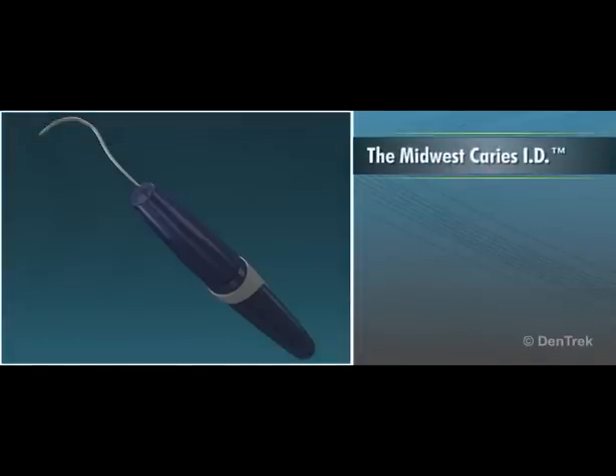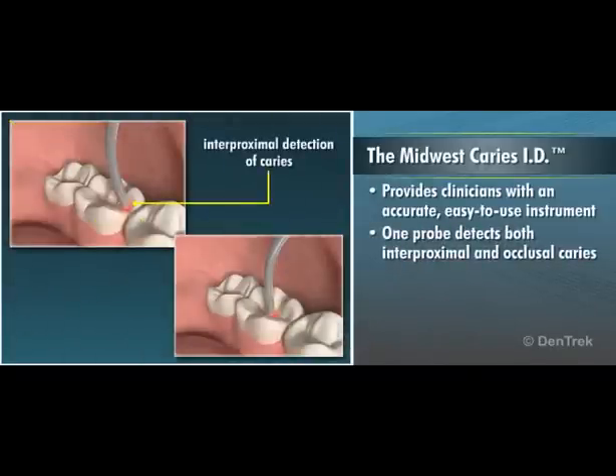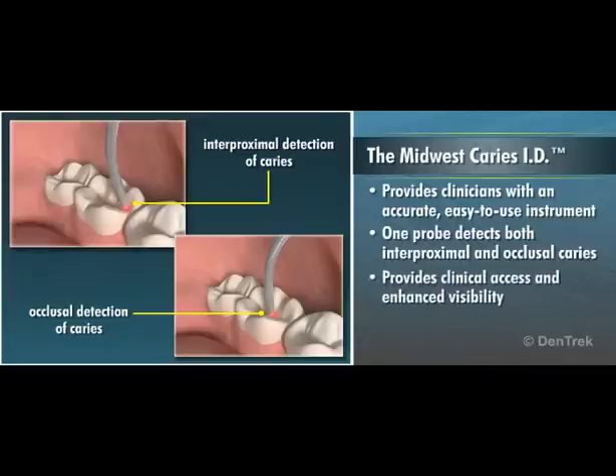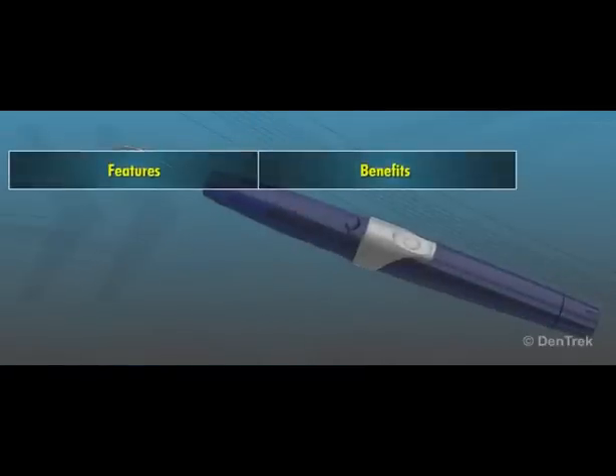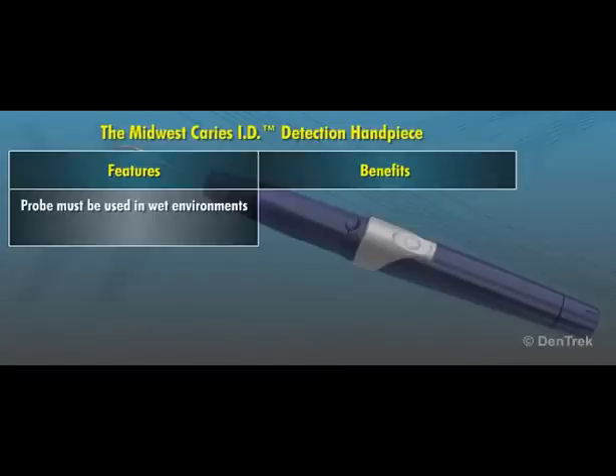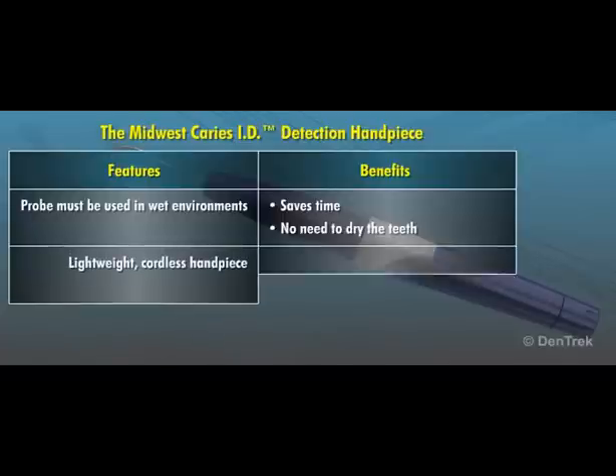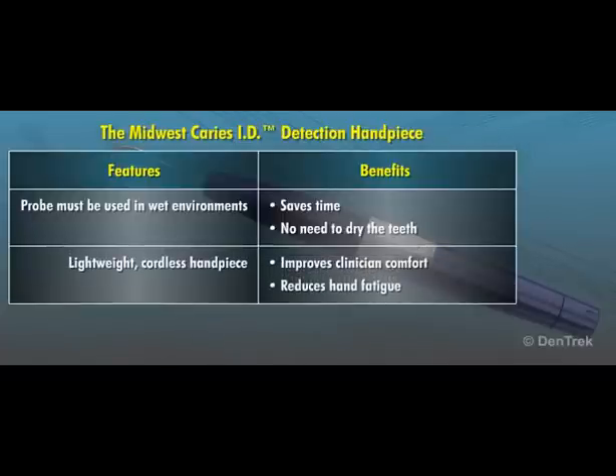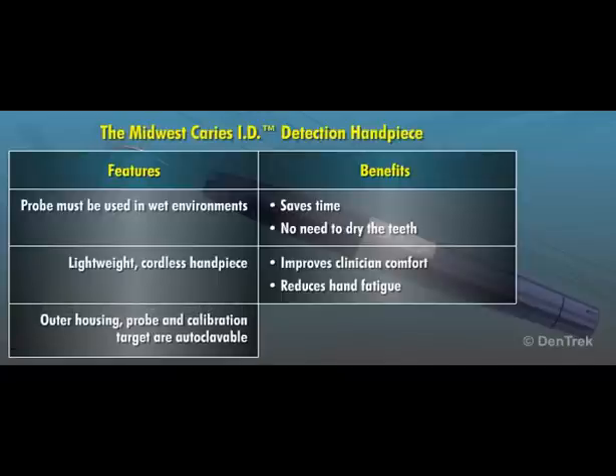The Midwest Caries ID detection handpiece provides clinicians with an accurate, easy-to-use instrument. One probe detects both interproximal and occlusal caries while providing clinical access and enhanced visibility, and the visual and audible caries detection signals provide an ideal end-user interface. The probe must be used in wet environments, so you don't have to spend time drying the teeth. The lightweight, cordless handpiece improves clinician comfort and reduces hand fatigue. The outer housing, probe, and calibration target are autoclavable, reducing the risk of cross-contamination.